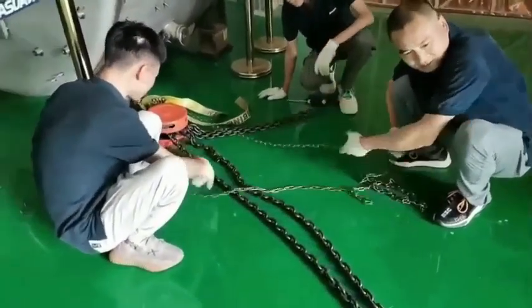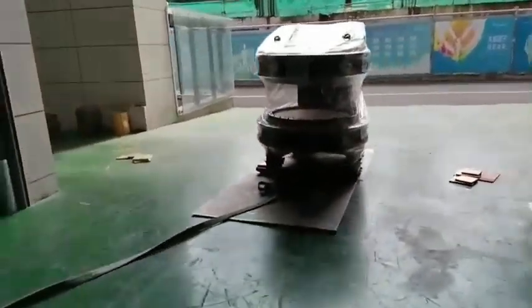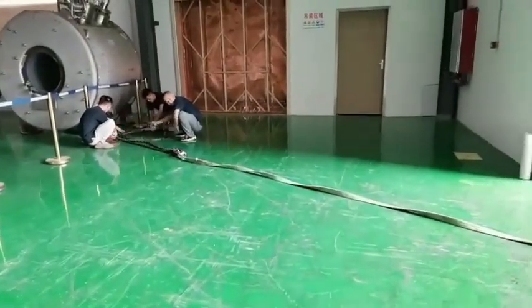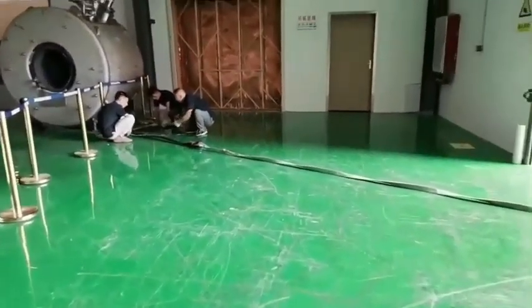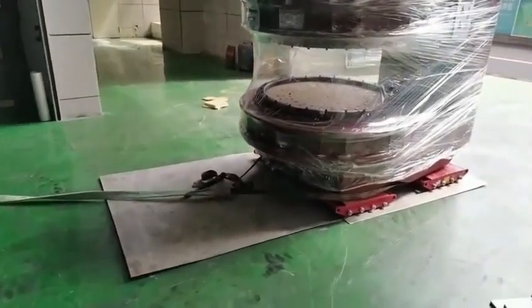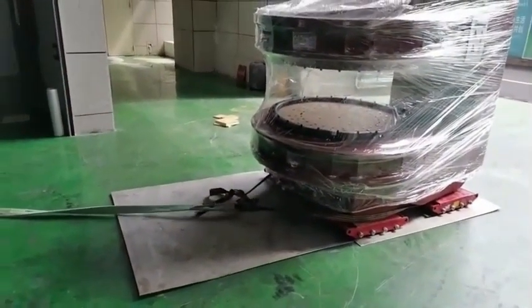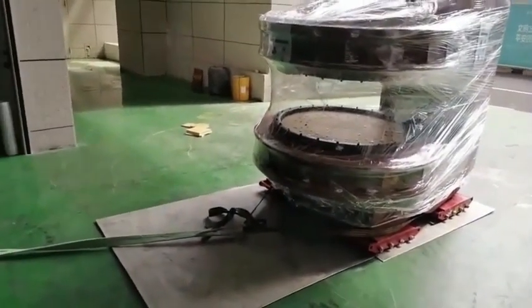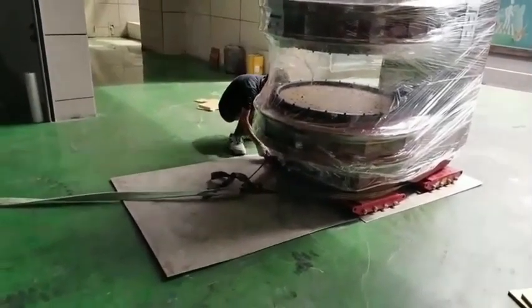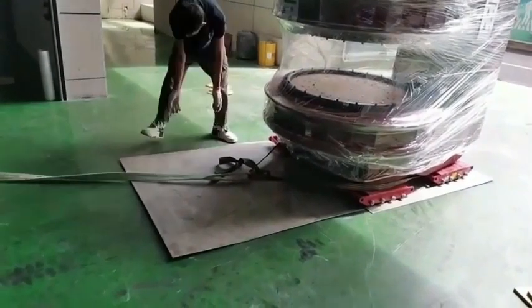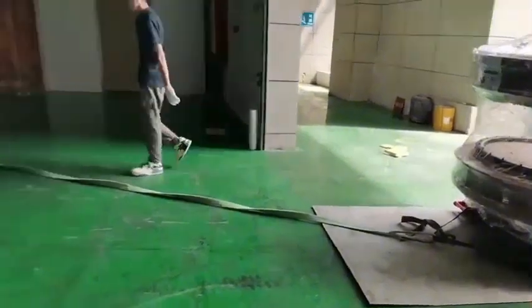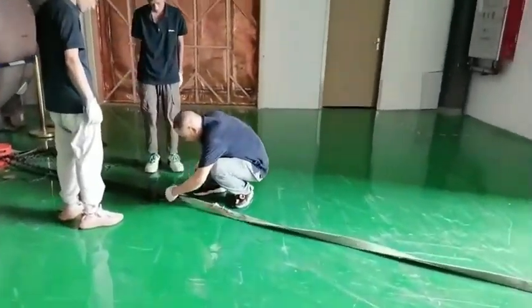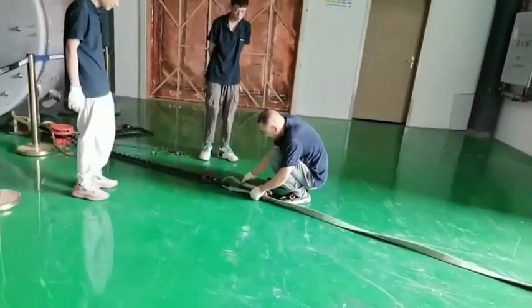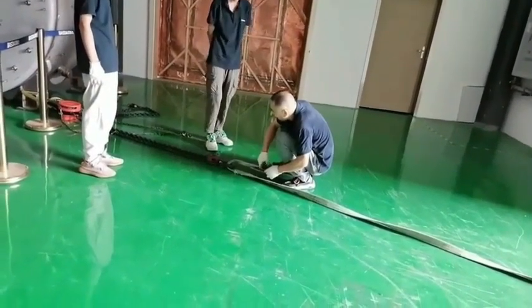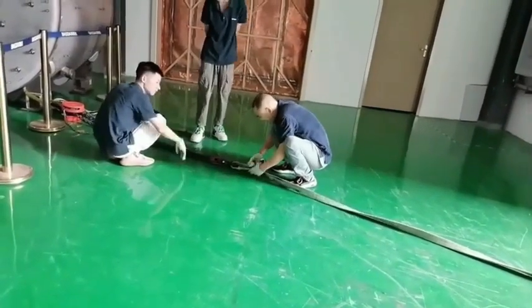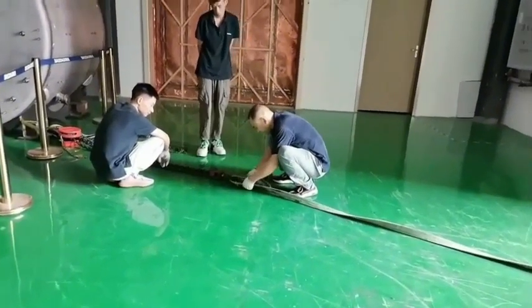When the anchor and the magnet are well connected by the cable, now the worker can use this pull hoist to drag the magnet slowly. And this structure makes the power multiple. The pulling power is multiplied by this structure. And now we make sure the iron plate is just in front of the magnet, entering the room. Make sure again the cable is firm enough.